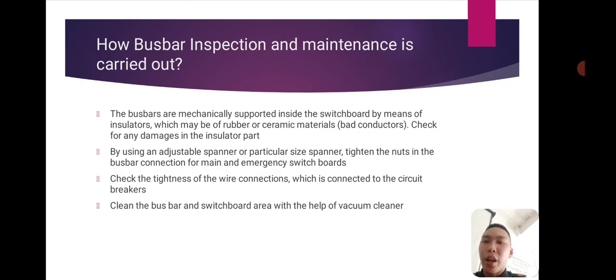The bus bars are mechanically supported inside the switchboards by means of insulators, which may be of rubber or ceramic materials, bad conductors, and check for any damage to the insulator part. By using an adjustable spanner or a particular size spanner, tighten the bus nuts in the bus bar connections for the main and emergency switchboards. Check the tightness of the wire connections which are connected to the circuit breakers. Clean the bus bar and switchboard area with the help of a vacuum cleaner.